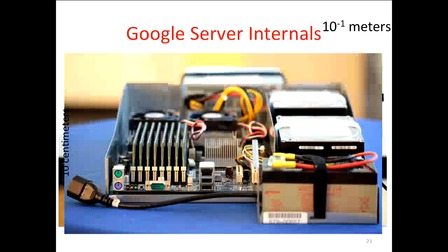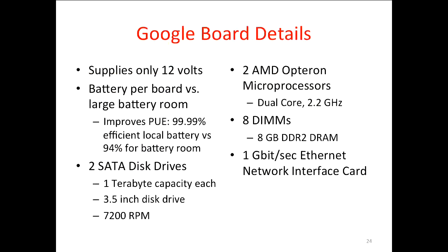And the thing is, though, when the lights go out, it takes a while for the generator to kick on. It takes a minute or two for that generator to get running and producing power. And they need batteries in the meantime, so the batteries just need to last long enough for the diesel generator to get going, right, to fill in the power supply. So that's one reason to have the battery, right? So you can run these things for a little while until the generator kicks in. But the other reason is pretty interesting. Let's just look at the details.